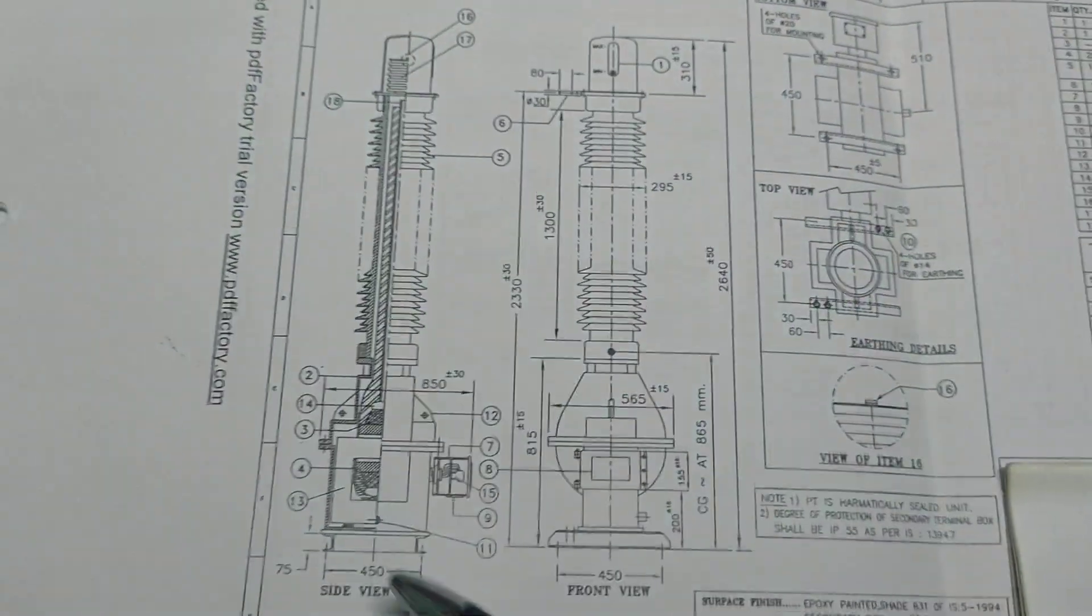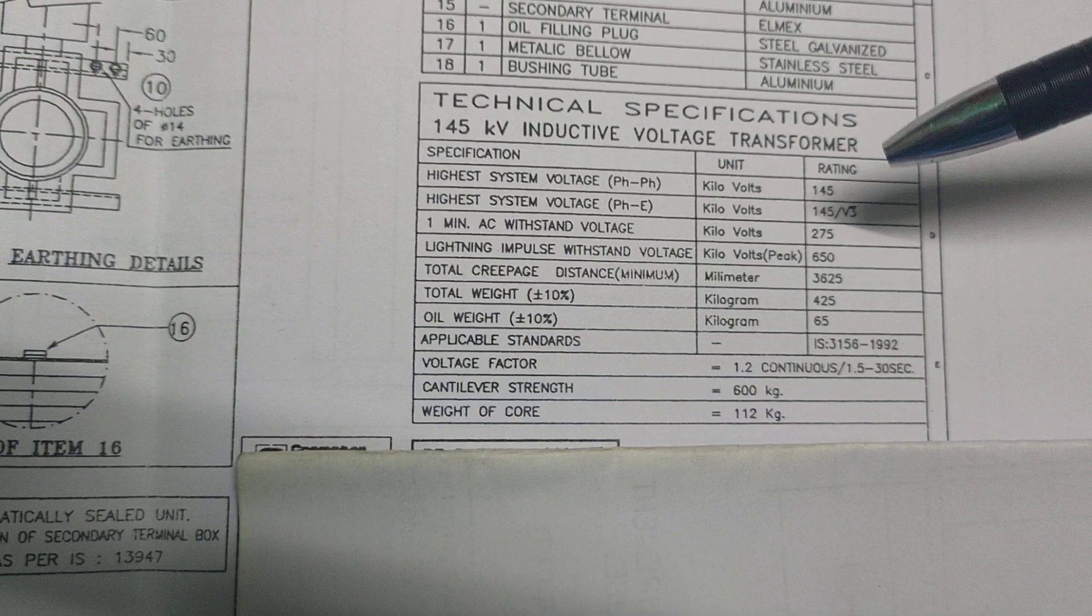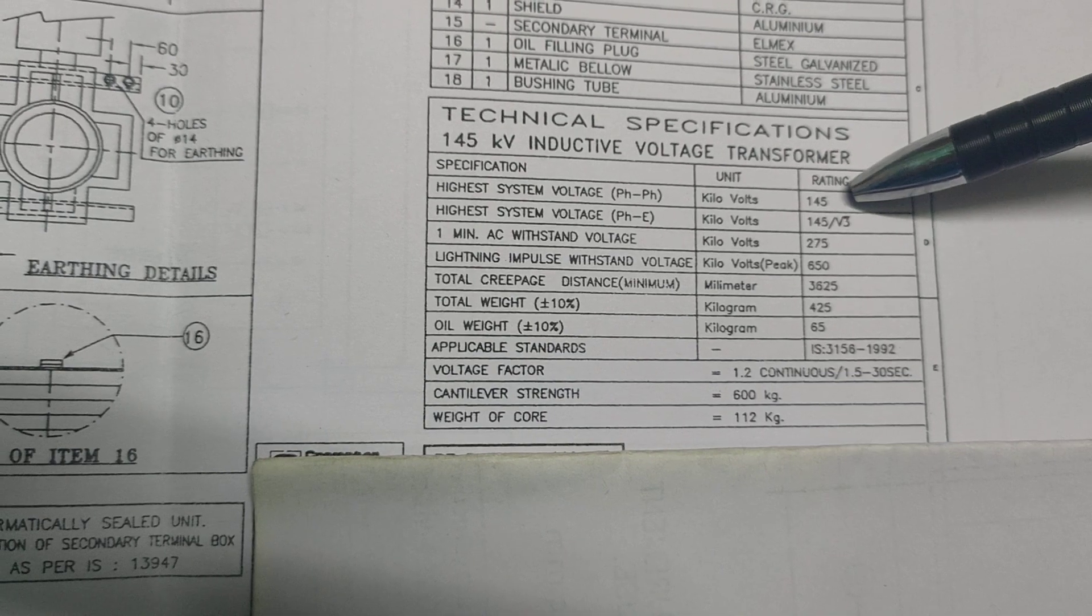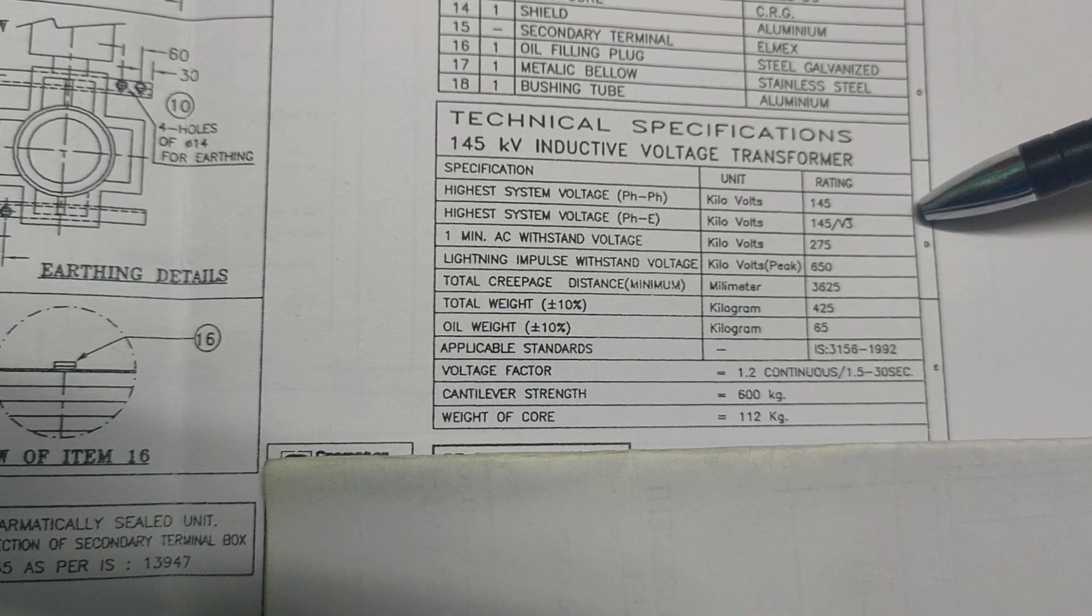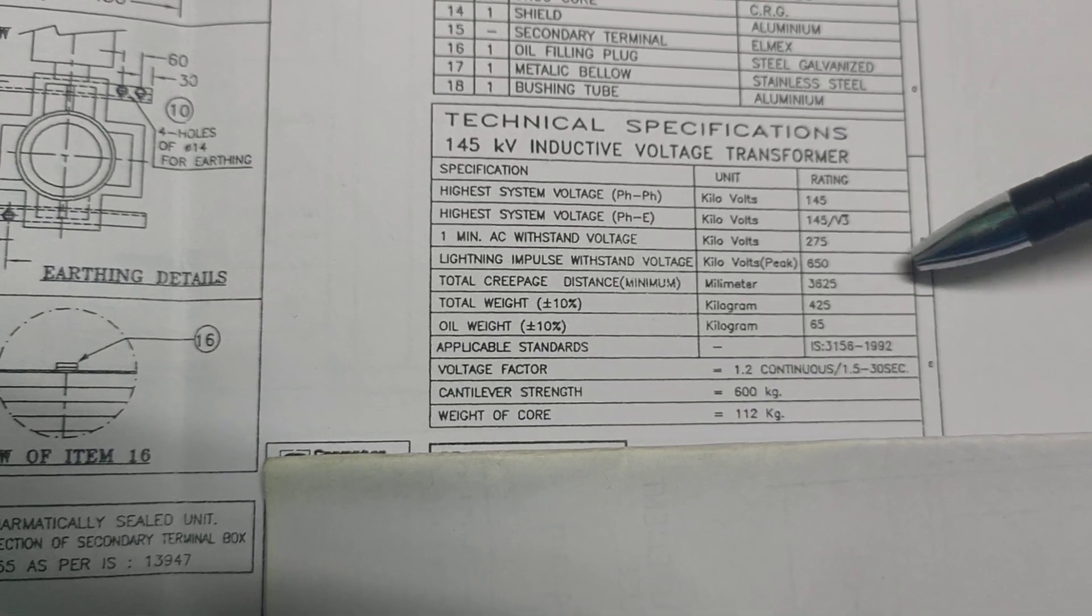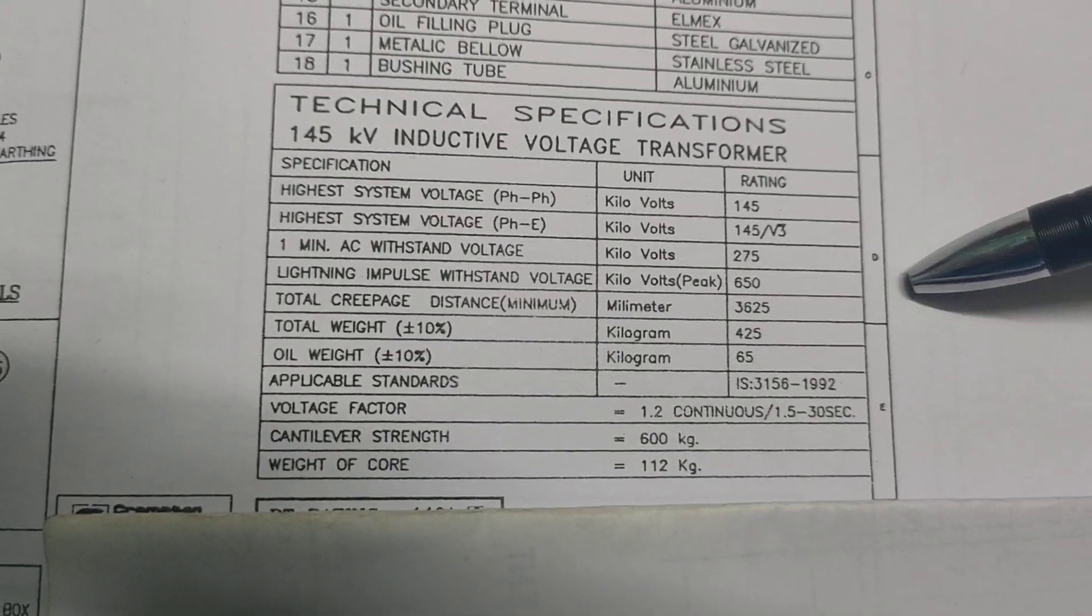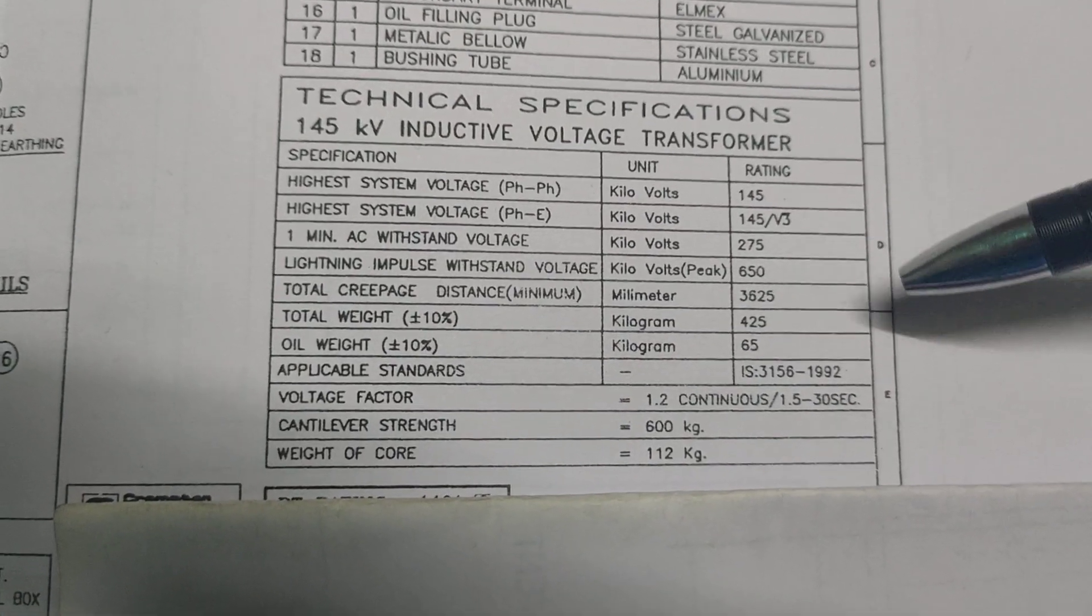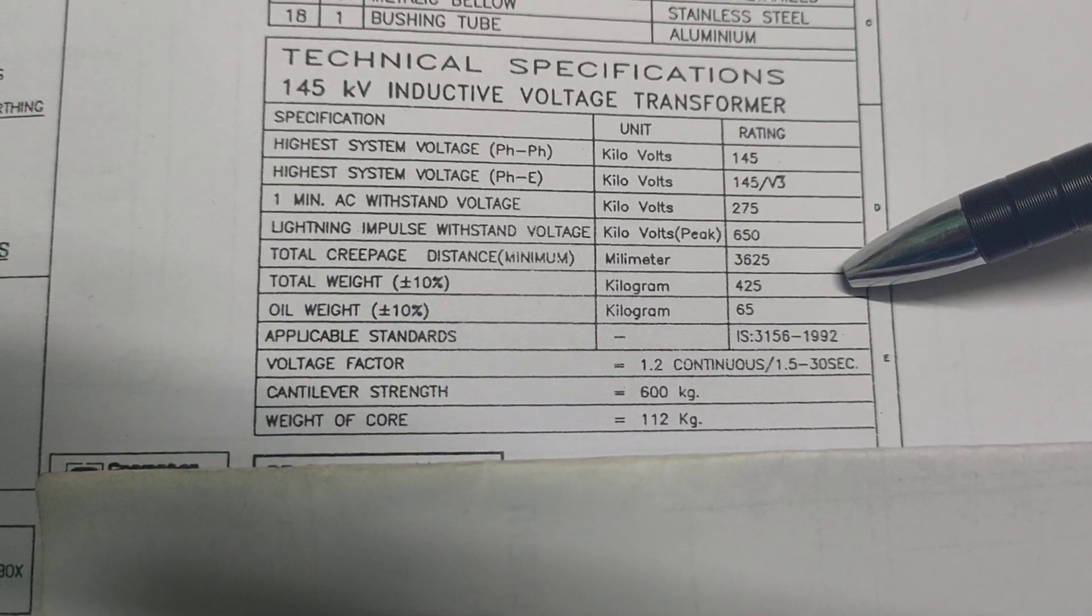Now we discuss the technical specifications. The highest system voltage phase to phase is 145 kV. Highest system voltage phase to earth is 145 divided by root 3. One minute AC withstand voltage is 275 kilovolt. Lightning impulse voltage is 650 kilovolt peak. Total creepage distance minimum 3625 millimeter.